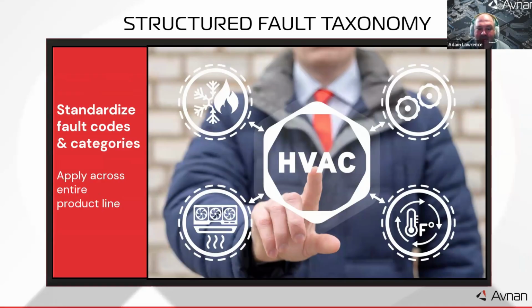The next key step in building this framework is creating a structured fault taxonomy, a standardized system of fault codes and categories consistently applied across your entire product line. If every product or every team uses different names for the same fault, it creates confusion. One model's software might log a damper issue as discharge air damper hunting, while another calls the same behavior damper cycling instability. This may seem trivial, but inconsistent fault naming leads to confusion and makes it harder to analyze issues across a fleet of equipment.